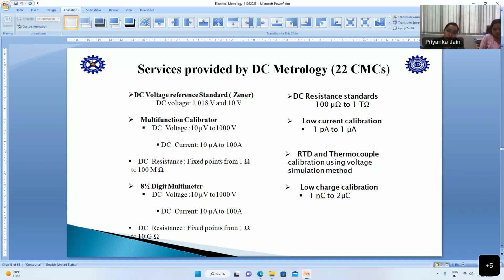One is low current calibration, that is 1 picoamp to 1 microamp. 1 picoamp means 10 to the power minus 12. We are working on 10 to the power minus 15. The R&D is still going on, but 1 picoamp we are able to deliver. From this range, we are getting many picoammeters, ammeters, electrometers, and dosimeters for calibration. This range is required particularly for the health sector. That is, radiation dosimetry defines the value of radiation dosage to patients. So for that, we are doing this calibration.